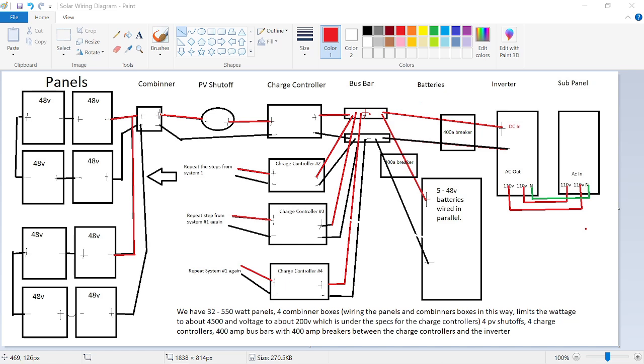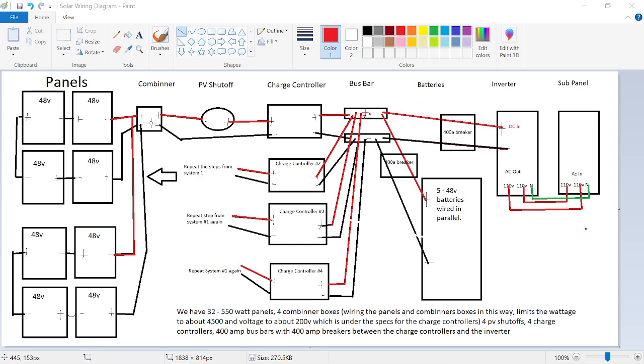We came out of the combiner box, came down to the garage, and we put in PV shutoffs, the red shutoffs. I'll show you a picture of this here in a minute. The PV shutoffs, okay, so there's four of those. So there's four combiner boxes, there's four sets of panels of eight each, four combiner boxes, which are combining the eight panels. So there's four in series, and then you put the two sets into the combiner box, and it parallels those together to keep your wattages where you need them for the charge controller, and also for the voltage for the charge controller.